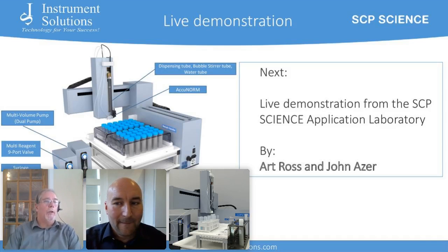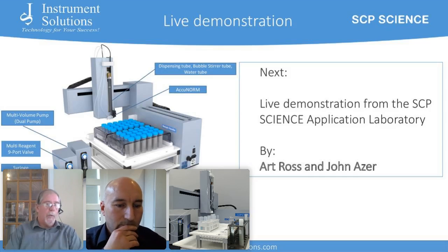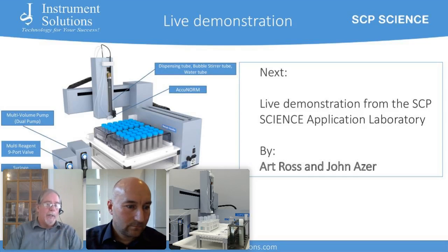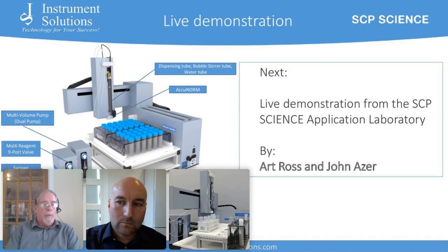Yes, that's absolutely right. And the assumption is that if you have your sample that has sediment on the bottom, when you go to aliquot it, we make the assumption that it's a homogeneous sample. If it's considered to be homogeneous, like we showed in the live presentation when we added the liquid to the system, when we looked at that quartz tube for microwave, you could see that we had great mixing in it. So we would assume that would be homogeneous. So if your sample is homogeneous, then you can just take your aliquot off of the top and then do your dilution without using the bubble stirring. And bubble stirring is an option that you can add or remove as required for your particular application.